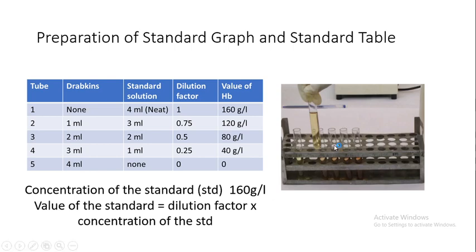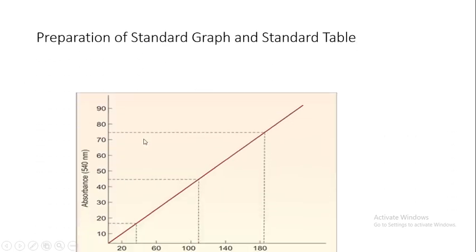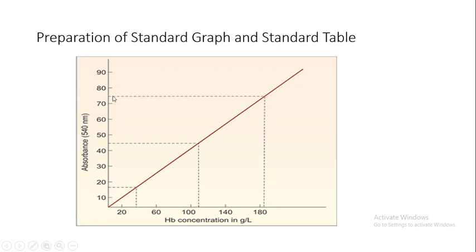Take the absorbance at 540 nanometers of the solutions prepared according to the table against the blank of Drabkin's solution. Using linear graph paper, plot the absorbance values on the vertical axis and the hemoglobin values on the horizontal axis. The points should be a straight line that passes through zero.